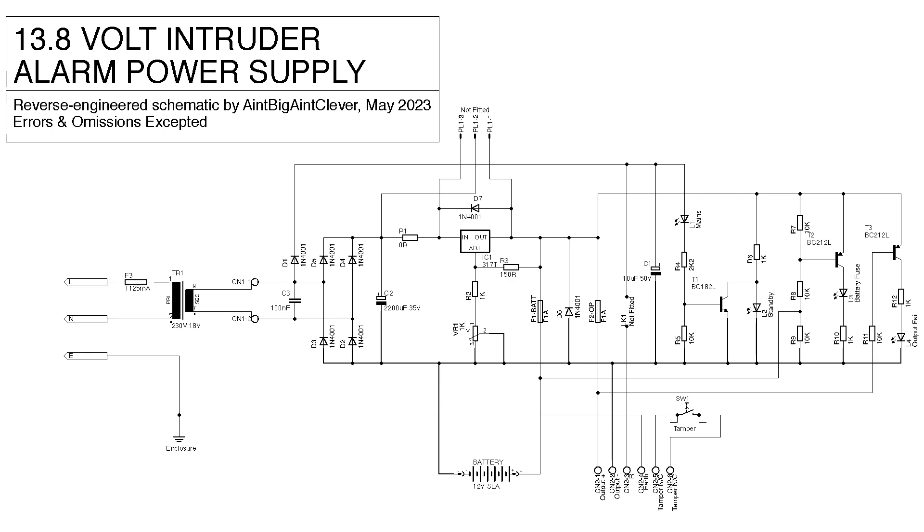To the right of the missing jumper link, which if fitted would provide a non-backed up supply on the front output terminal marked R, is the circuitry which deals with the front panel LEDs, plus the tamper switch which would alert an alarm system if the lid was opened. That non-backed up supply feeds mains LED L1 and through that the base of T1. If the mains is on, L1 will light and T1 will shunt standby LED L2 turning it off. If the mains is off, L1 goes out, T1 turns off and L2 is lit as this gets power from the battery backed supply.